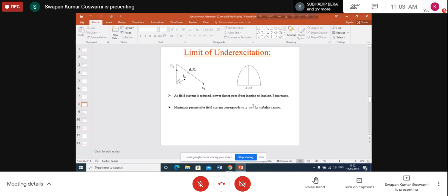So what power will they be absorbing? They will not be absorbing active power because there is no resistance. So they will be absorbing some reactive power. What reactive power? Obviously it is negative reactive power. That means if the series reactance is consuming reactive power, obviously you can say that shunt capacitors will be generating reactive power. So the shunt capacitors are always generating reactive power during the 24 hours of operation.